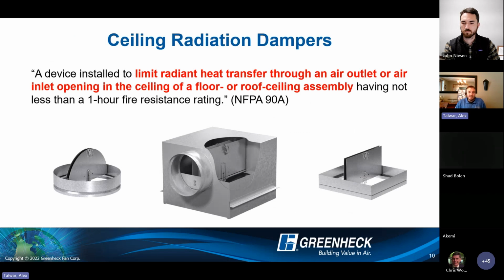And I do have a couple slides here on ceiling radiation dampers. So a little bit different than a fire damper, although they do also have a fusible link to hold them open. But the products currently aren't really tested to close against any dynamic airflow. And really the purpose is not necessarily to restrict the spread of flame, but to restrict the spread of radiant heat transfer into a floor ceiling or roof ceiling assembly.